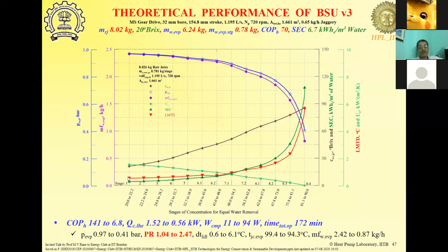Simulation was done, and as you can see here, initially the sugar concentration in the solution is low, so the boiling point elevation is also low. And the LMTD is also low, because the heat transfer coefficients are much better at low concentration because of low viscosity. As the solution concentration goes up, it becomes very viscous, and the heat transfer coefficient drops from more than 2000 watt per meter square Kelvin to around 50-60 watt per meter square Kelvin. So the delta T, the LMTD required to transfer the heat, increases significantly.